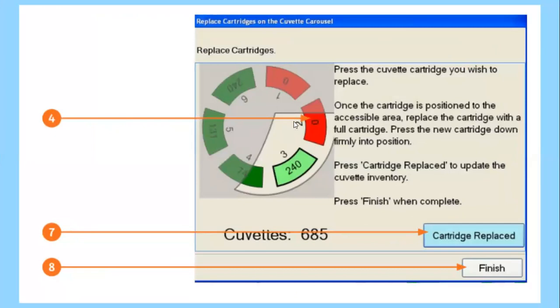This screen has 2 red ones. If there are out, they will say 0. The number that they have total will be remaining in the green. So what you'll do is you'll just tap on the red, and it will rotate the wheel that the cuvette cartridges are on, and we just open the door and take out the old one and just replace it with a new one. And once that is done, you hit Cartridge Replace in blue, labeled by number 7, and then you hit Finish, which is labeled by number 8. Let me go back.